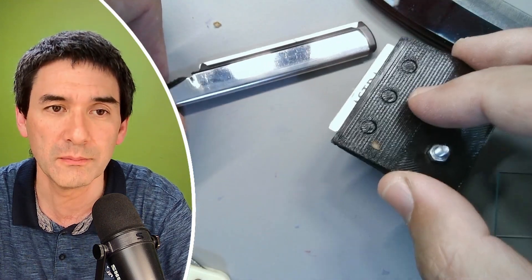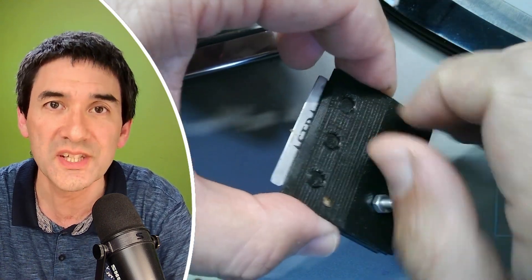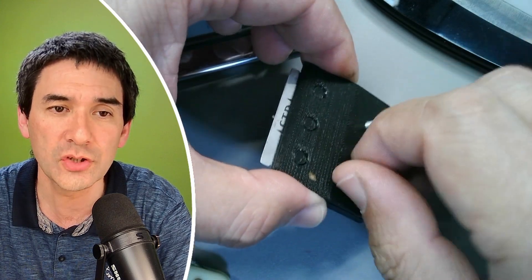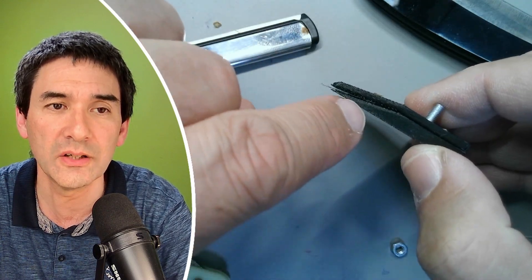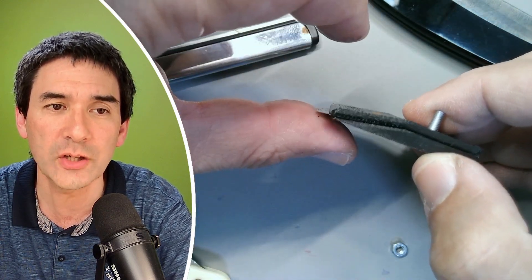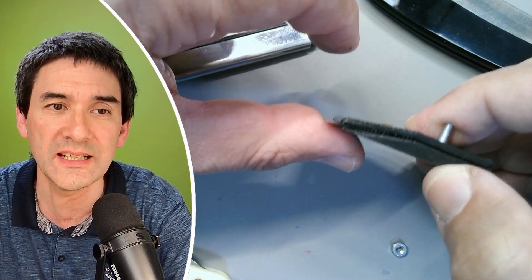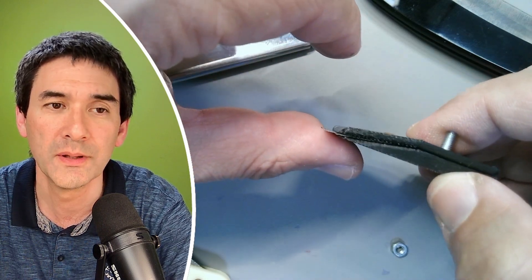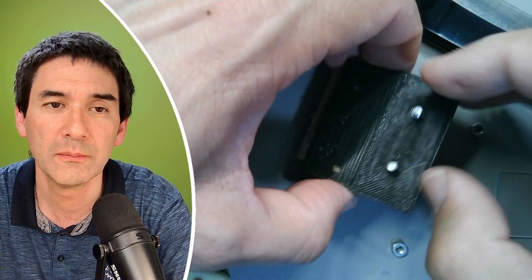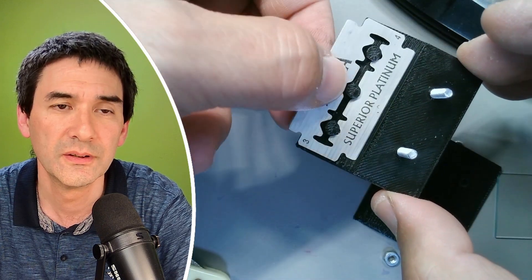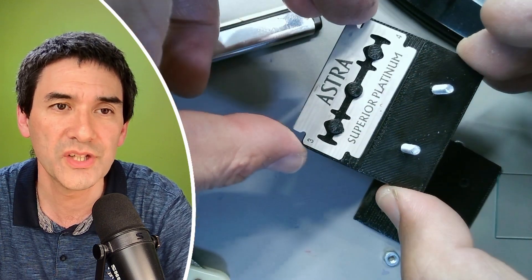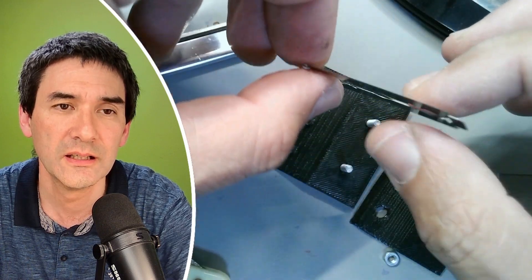My suggestion would be indeed to experiment around with disposable blades and I found this one to be the most consistent one. I just want to show you why this is so important because you see there's a certain angle here. This means that the blade will actually press lightly against the surface of the microtome so it will bend up slightly. In here when you open it up you can actually see the blade and it can also be turned around. You can also see here now how extremely flexible it is and this is something that makes it unsuitable without a holder.